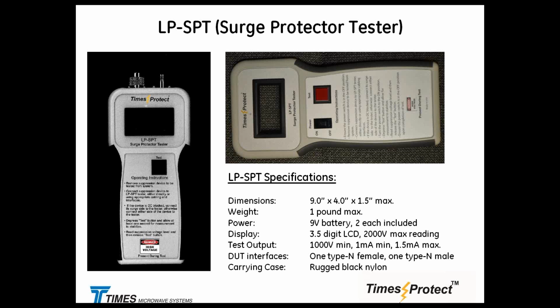So after debating that for a number of years, we came up with a little handheld tester. This is a prototype picture. We're going to be launching that very soon. We're going to have a couple of N connectors, female and male, and we're also going to come up with little alligator clips, two clips with an interface, which you could use to test varistors or data line protectors or anything with terminals other than RF terminals. And basically, you turn the power on switch here, you depress the test button.